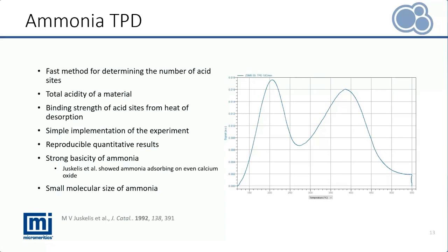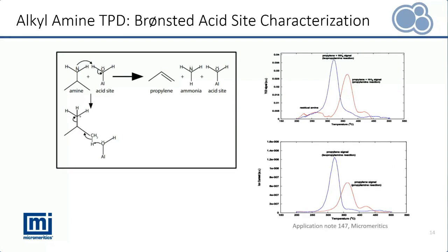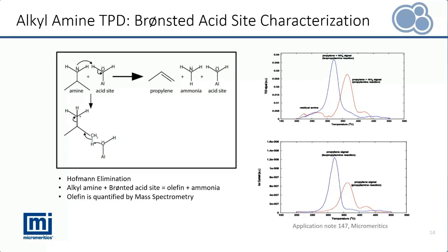On the right, here is a good example of an ammonia TPD at 10 degrees Celsius per minute ramp, analyzed on the AutoChem 3. We can immediately see the two different acid sites present, and the ammonia desorbed can be integrated by calibrating the TCD signal, which gives insights to the acidity of each acid site. On the other hand, we can use alkyl amines as probe molecules in contrast to ammonia. They are protonated by the Bronsted acid sites and decomposed by Hofmann elimination into ammonia and olefin. The olefin mass spec signal can be calibrated and quantified, hence the Bronsted acid site can be quantified.